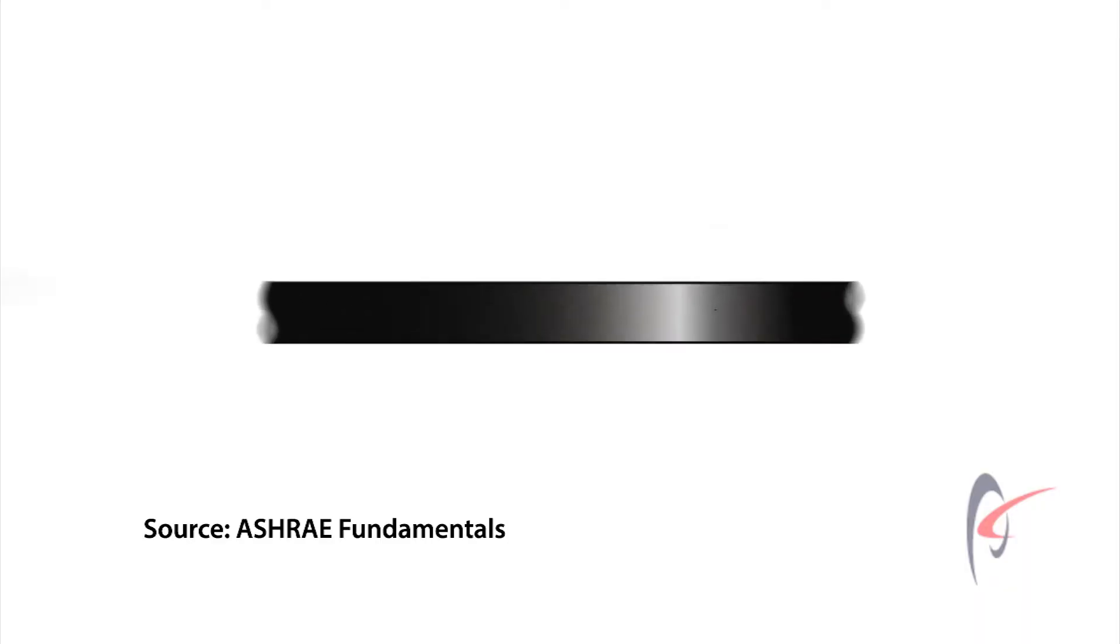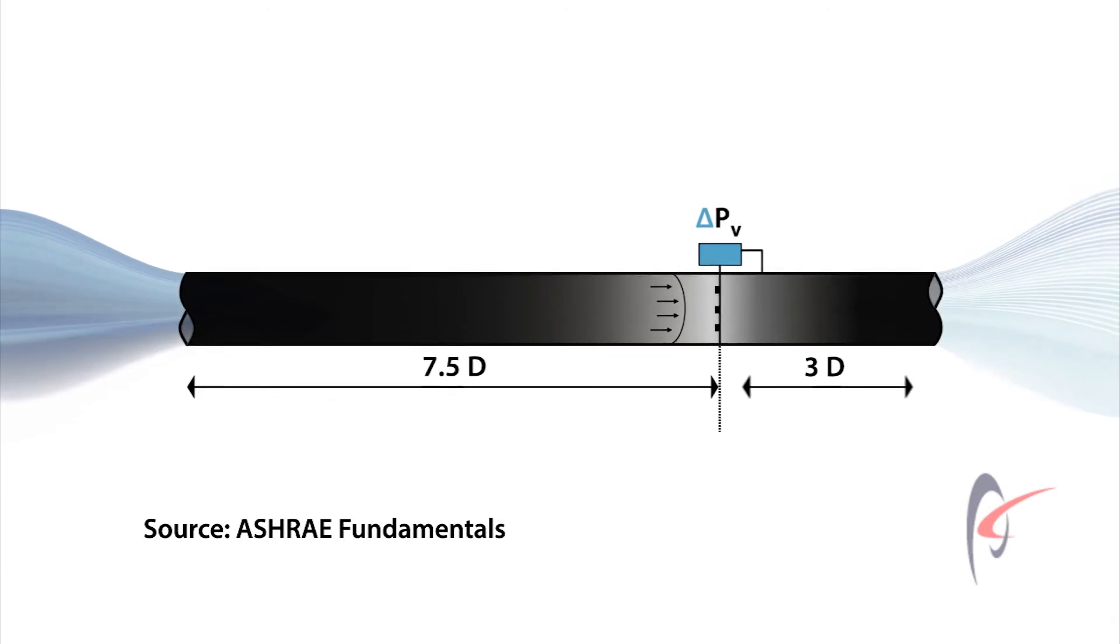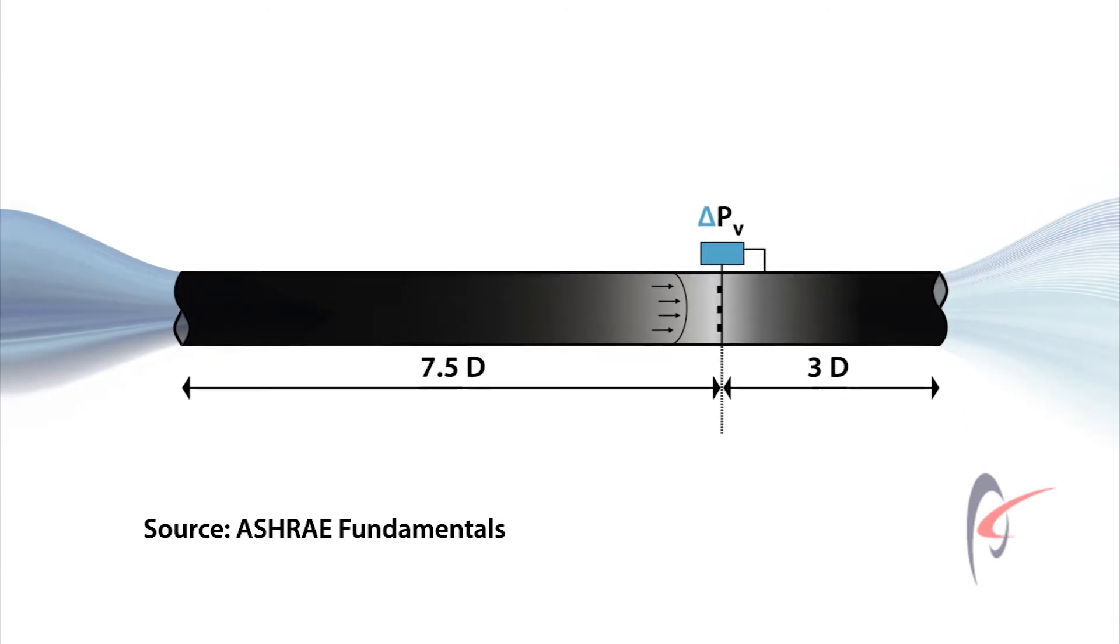With a VAV box, per ASHRAE design guidelines, they need 10 duct diameters of straight duct, seven and a half on the inlet side and three on the outlet side to get as accurate as they can possibly be. That's just not really obtainable in the built environment today.